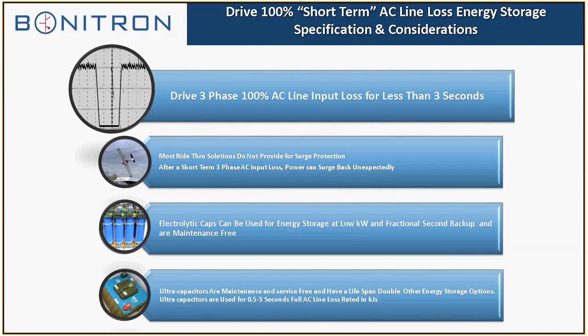So it depends on how bulletproof the customer wants to be, and it depends on the amount of utility power events they want to cover. It's usually a trade-off between making the system fully bulletproof and covering a percentage of the utility power events. Because maybe if you cover 90–95% of the utility power events for a customer, that's enough to get them past their losses and their downtime that they were looking at. Because that's what you weigh the cost of the ride-through against: customer losses in products, downtime, personnel safety, things like that.